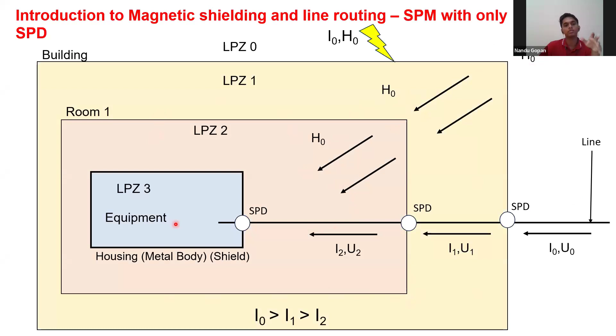But since I have good SPDs, this will reduce I0 to I2, but H0 will remain the same. This is most of the scenario in India: we have done good SPDs, and we have also connected most of the RCC steel sometimes. Even if you are not connecting it, there will be a significant reduction from H0 to probably H2. But if you are doing construction without RCC steel and have not done shielding, then the magnetic field, even with a good SPD, might not be enough to protect the equipment. That is the key point here.